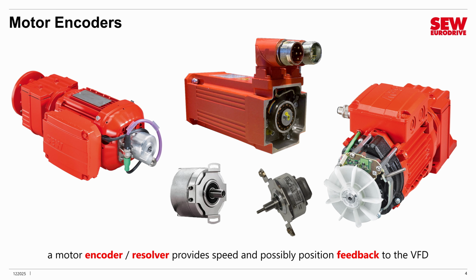A closely related topic that we do need to think about is whether or not the motor has an encoder or a resolver which provides speed and possibly position feedback to the VFD. While it is certainly possible to run a motor without feedback, you can get far better results if it's available, and when you're doing positioning, it's usually essential. This picture shows a variety of motor encoders and resolvers. They all attach to the end of the motor shaft in some way.